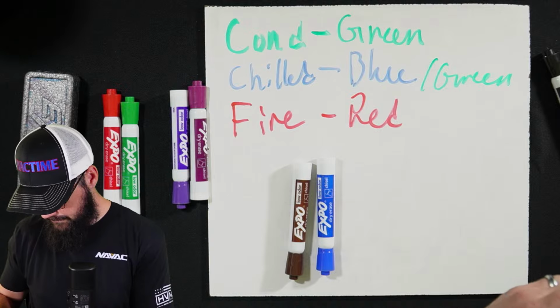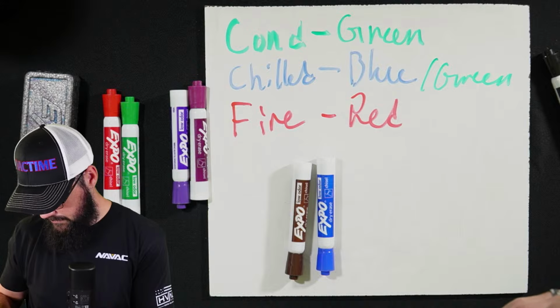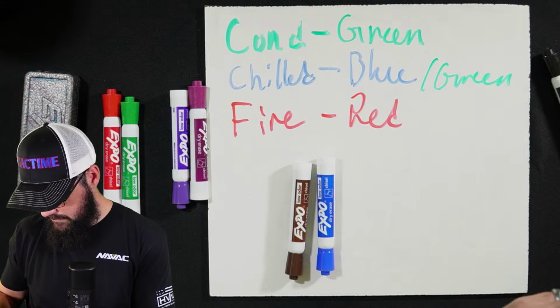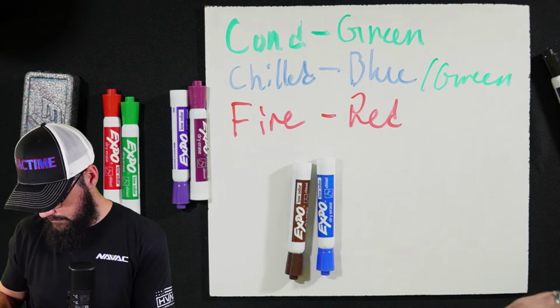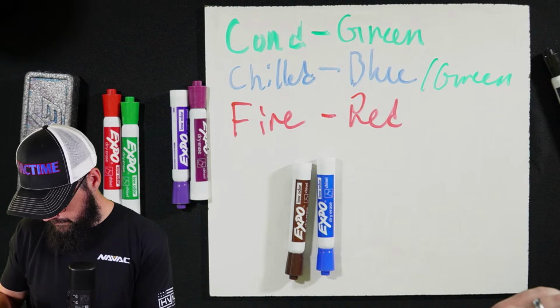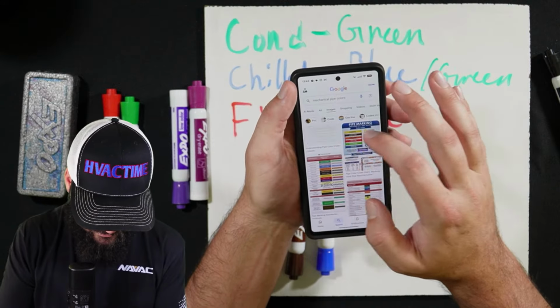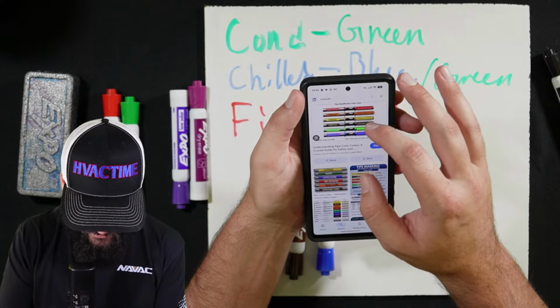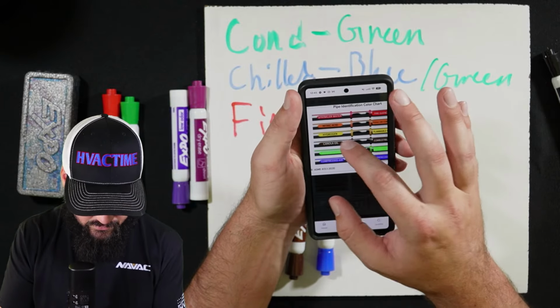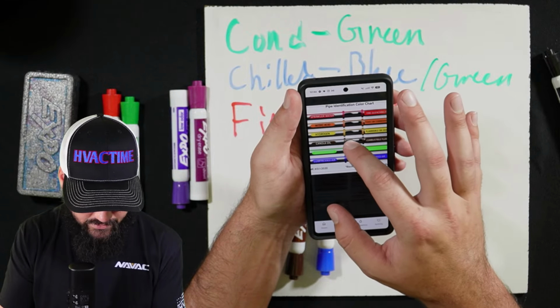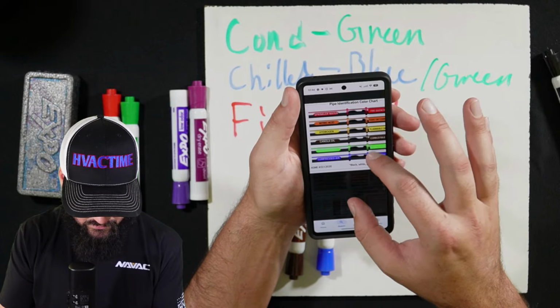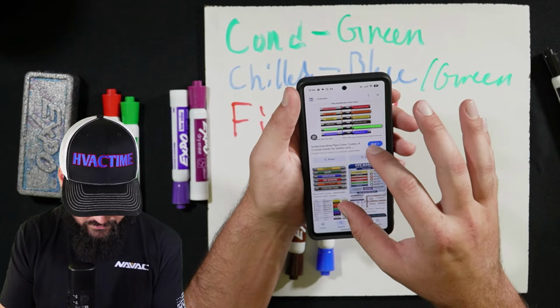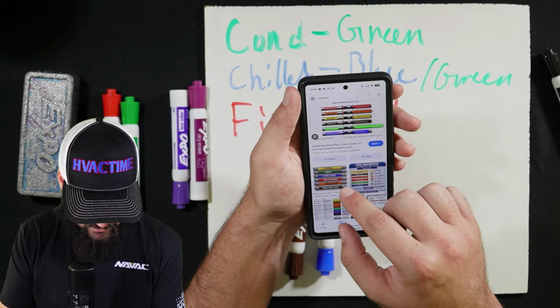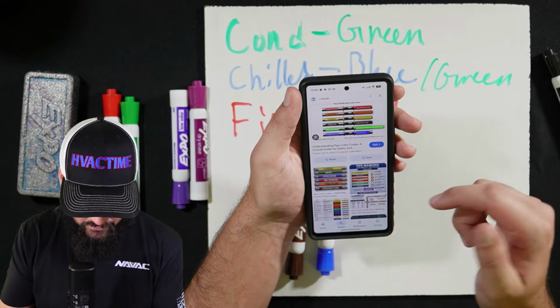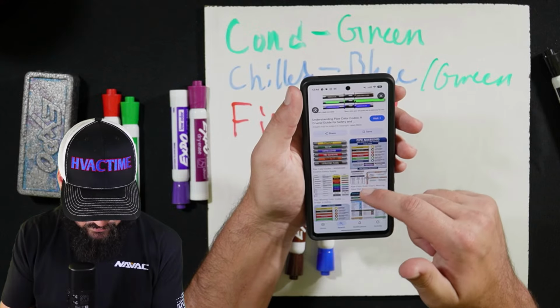Let's see. Plant. Or mechanical pipe colors. How about that? Mechanical pipe colors. Yes, here we go. So, yeah, sprinkler water, which is fire, is red. Yeah, compressed air is blue. That's right. Boiler or condenser water is green. And there is a difference between potable and non-potable water on the codes.